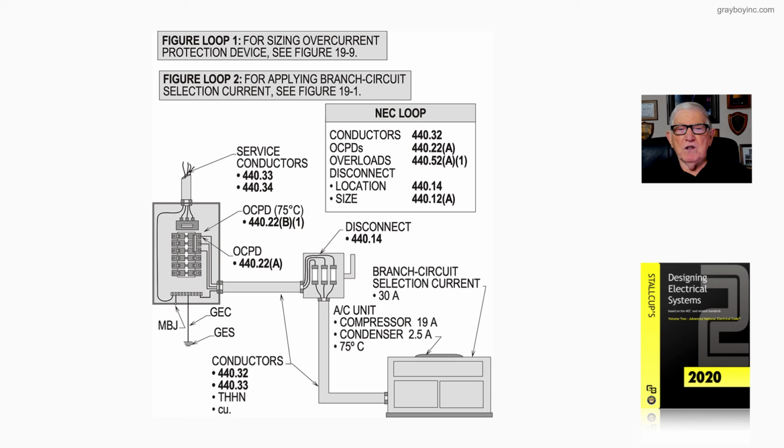The overcurrent protection device, and we're looking at 440.22(B)(1), and we're looking at 440.22(A) since it's one individual unit that we want to review here. Now, based upon that, then, we're going to select the overcurrent protection device based upon our calculation, and we will look at that next.